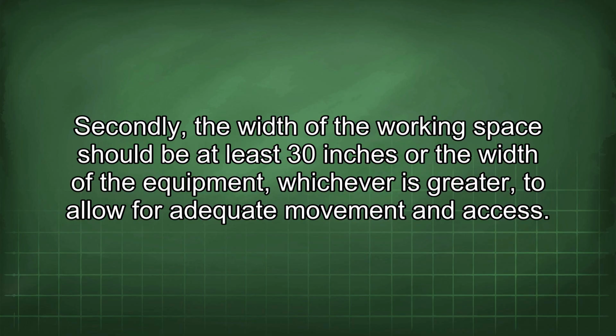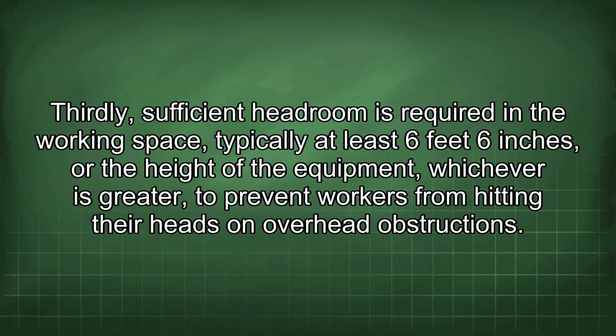Secondly, the width of the working space should be at least 30 inches or the width of the equipment, whichever is greater, to allow for adequate movement and access. Thirdly, sufficient headroom is required in the working space, typically at least 6 feet 6 inches, or the height of the equipment, whichever is greater, to prevent workers from hitting their heads on overhead obstructions.